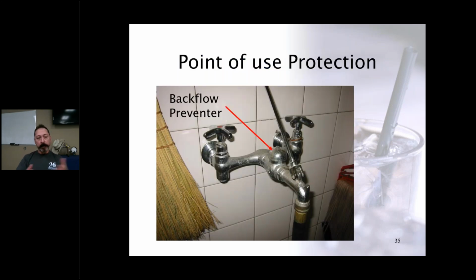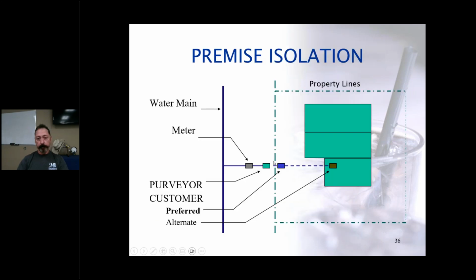So internally, this is just an example of a utility sink, which is pretty common. And there's a backflow preventer called an atmospheric vacuum breaker built into the fixture. So it's integral to the fixture. That prevents anything from getting sucked up into the drinking water supply from filling up the mop pail or whatever.